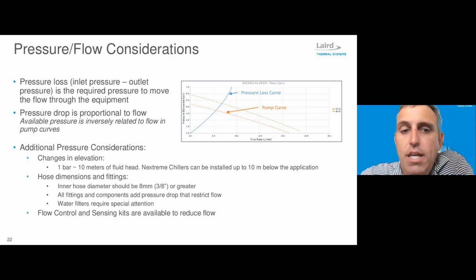And so there are other things that we need to keep in mind about pressure. Elevation change is another one. Now, in pumping systems, when we're pumping up to an application and then the flow is coming back to the cooling system, yes, it takes additional pressure to pump that fluid up, but we get that additional pressure back for free when gravity does its work to pull the fluid back down to the system. But the one thing we need to keep in mind is that we need to be able to deliver that flow the first time. So if there's a system install that's pumping up a number of stories, say 30, 40 feet, we need to make sure that pump can create that additional head, that initial head, in order to deliver the flow up the first time.